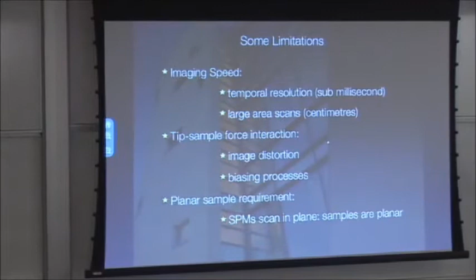The second thing is there's no low magnification. In AFM, we have to take a window and scan it round. Unlike electron microscopy or optical microscopy, where you can zoom back and get the whole sample in, we can't do that with atomic force microscopy. We're stuck with about 100 microns square. And so if we could go faster, if we could push the speed up, we could start taking lots of images quickly and building up a large area. So the speed improvements are important.